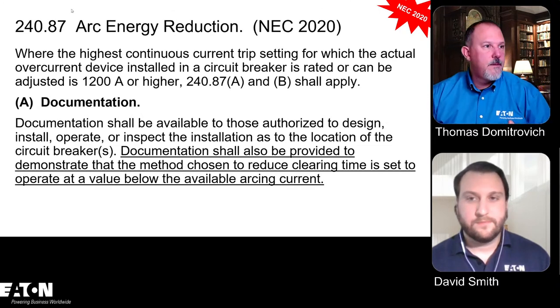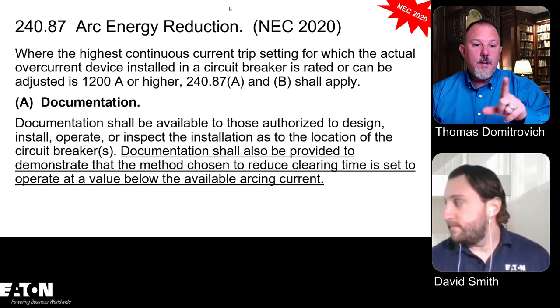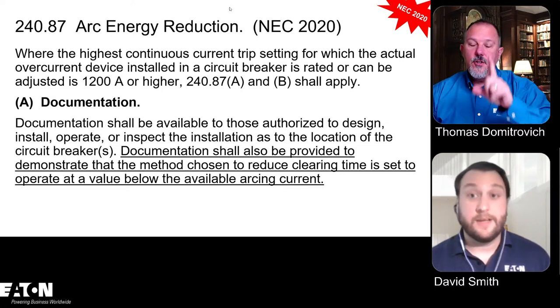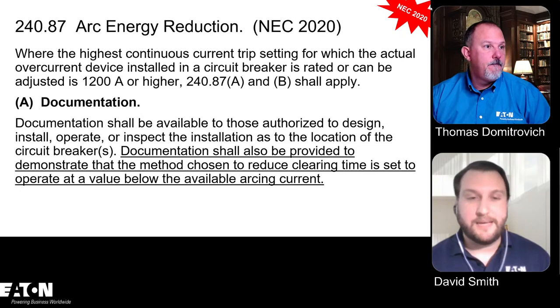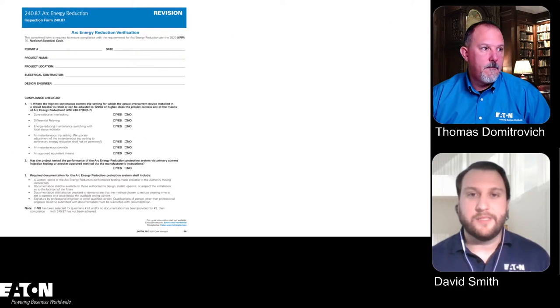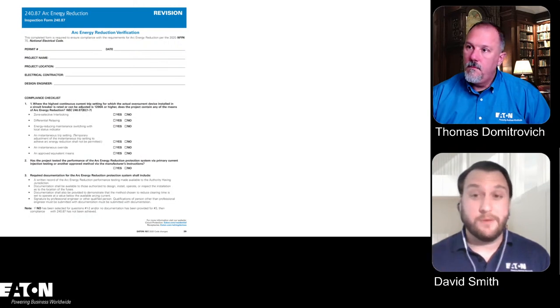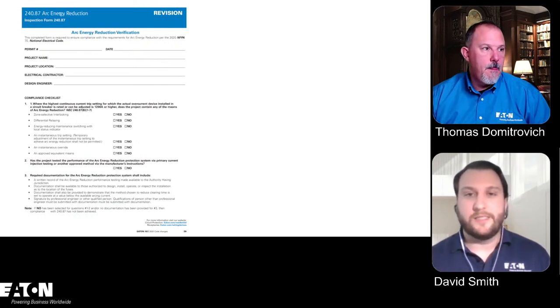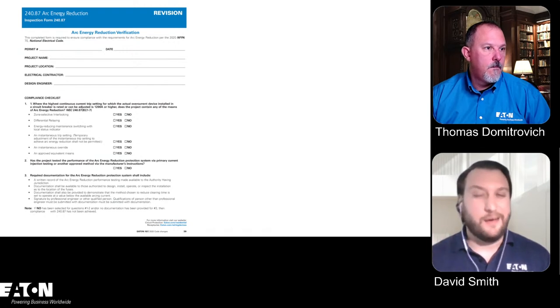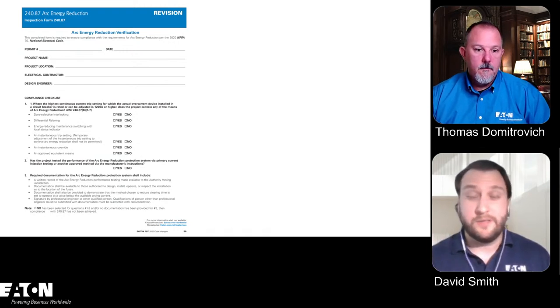Now you came up with a good checklist, right? Yes, absolutely. So one of the things that Tom was talking about at the beginning of this particular video is that we came up with a document. Number one, Eaton has a 2020 NEC code change document that I believe Tom is going to put in the description of this video. In that, under 240.67 and 240.87, you're going to be able to find this document in the PDF that has to do with arc energy reduction documentation.